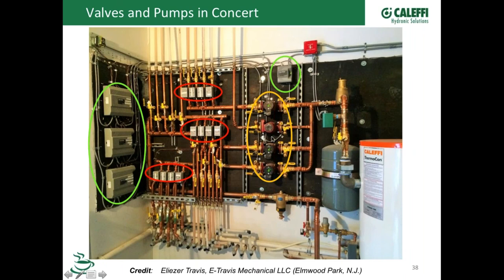Yeah, and some of the boiler manufacturers actually will give you that control in the boiler. If you put a second pump on the boiler, all the pumps shut off, the boiler pump shuts off, all the secondary pumps shut off, and then it just flows from the boiler directly to the indirect tank at that higher temperature, say 180 degrees, and shuts off. So you'll have a little slug of hot water there, but it's got a dedicated control. The boiler knows when there's a domestic hot water call and shuts off the main circulator to the buffer tank. So again, there are different ways you can do that. It just depends on your goals and what the customer's expecting.